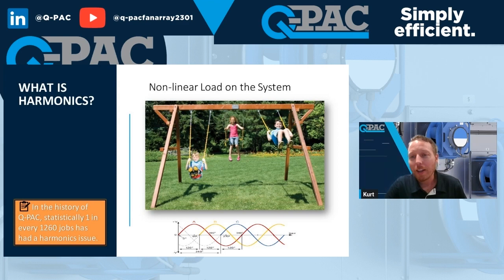And another thing to mention, a lot of people reference IEEE 519 for harmonics. That is a standard at the point of common coupling and not a component standard, which means that whenever you're checking for harmonics, you need to check at the transformer that's feeding many, many devices in the building, and not just a component. The components can add up and cause a lot of disturbances at the point of common coupling, but as I have in a note here, in the history of Q-PAC, we've had 1 in every 1,260 jobs have a harmonics issue, so it's not common.